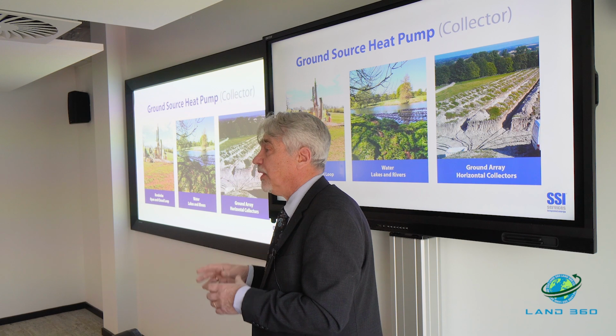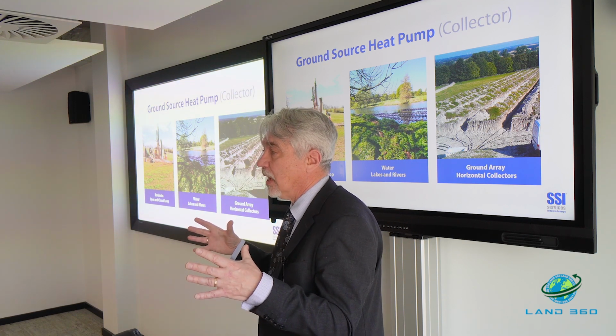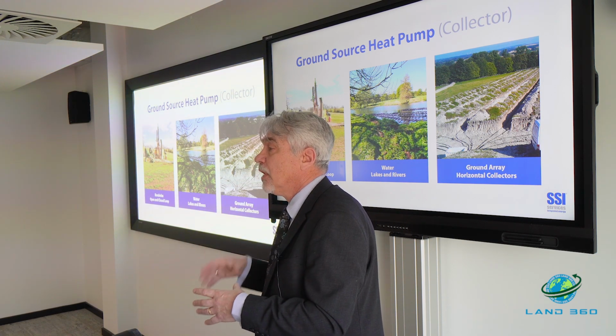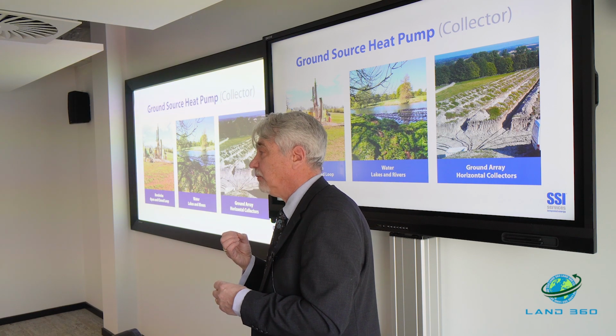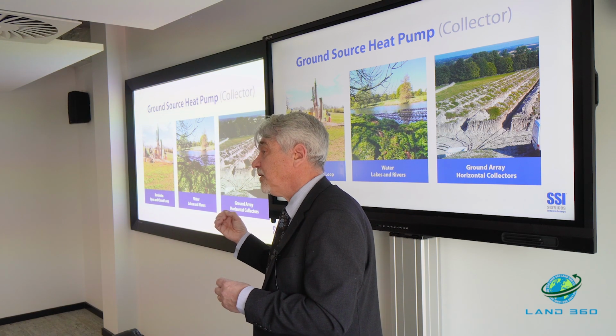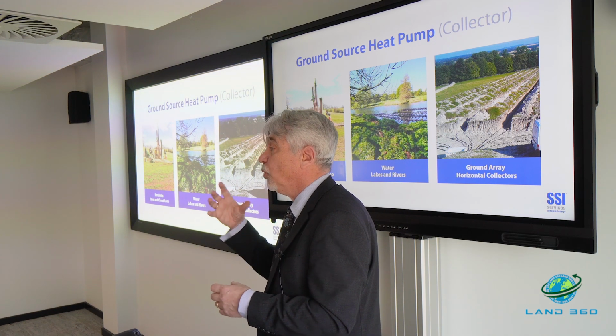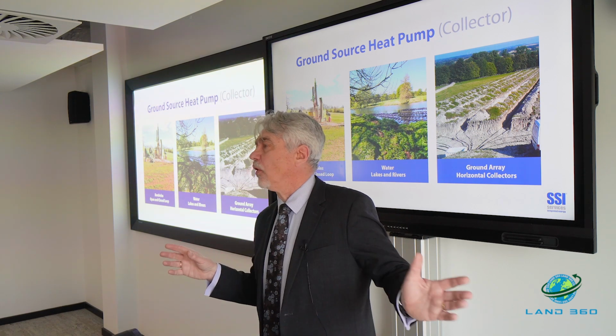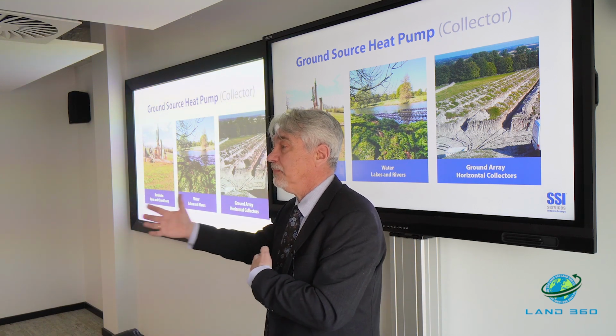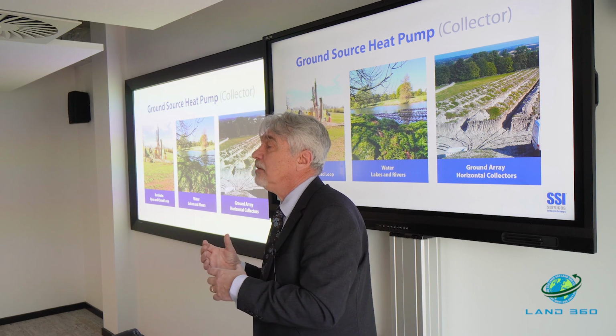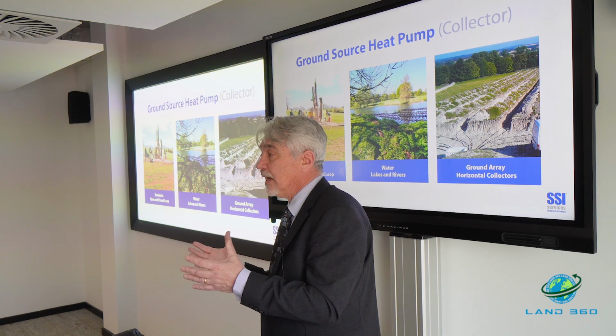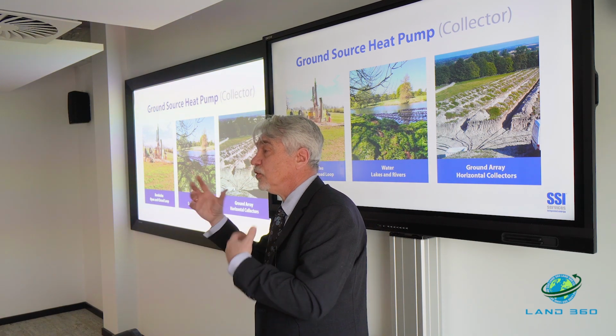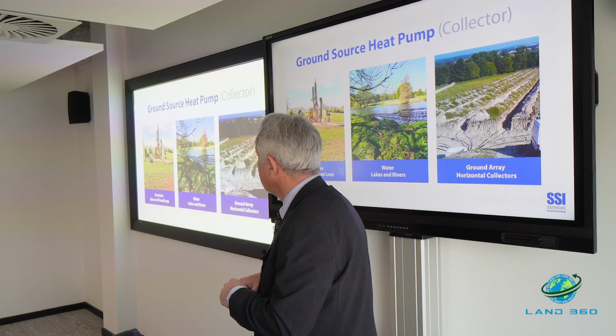An open loop is where you drop the borehole, slightly bigger diameter, into an aquifer. You abstract the water out of the ground, pass it through a plate heat exchanger, take the energy out of it, and then put that water back into the ground something like 100 metres away so it doesn't affect the aquifer. All you're taking from that water is the energy, not anything else, and it's easier to just drop it back into the ground.